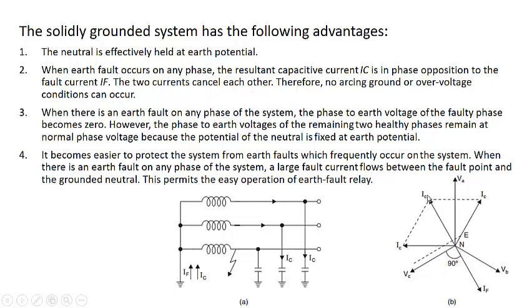There is not a sufficient current which may result in arcing ground or overvoltage, and the overvoltage condition is eliminated. When there is a fault on a phase, the faulty phase voltage becomes zero. However, the phase to earth voltages of the remaining two healthy phases remain at the normal phase values because the potential of the neutral is fixed at earth potential. And one more thing, since this is connected to the earth, when this phase C is touching the earth, there is a huge current flowing through it, which is even greater than the load current. In that case, the earth fault current is quite easily detected by the protective relays, and this can be disconnected from the system.